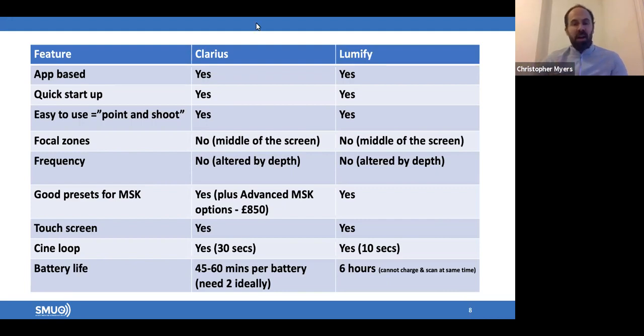On the Lumify, they have obviously the musculoskeletal preset option, but they don't have the option to then preset per joint. And that is the same on the basic package for Clarius, but for £850, then you can get this thing called an advanced MSK package, which means that you can not only have a musculoskeletal preset, but you can break down the presets per joint, which is personally what I would want to have. But if you're new to ultrasound, normally when you're new to ultrasound, you're just trying to get a machine to get started, I would suggest that the extra £850 is not worth it. You're going to get a good enough image quality, and I don't think the advanced MSK package is necessary. If you've got a spare £850, then obviously pop it on.